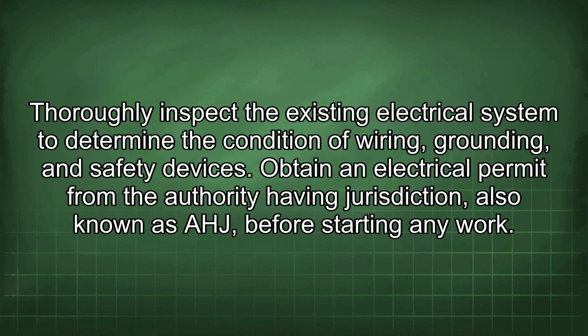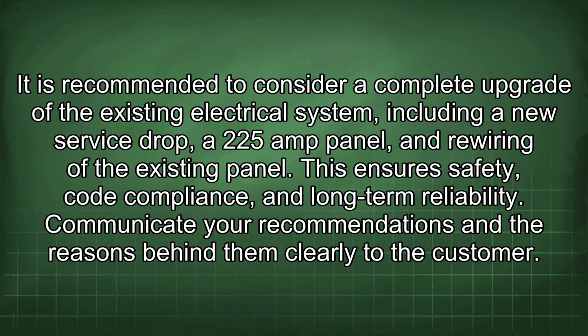Thoroughly inspect the existing electrical system to determine the condition of wiring, grounding, and safety devices. Obtain an electrical permit from the authority having jurisdiction, also known as AHJ, before starting any work. It is recommended to consider a complete upgrade of the existing electrical system, including a new service drop, a 225 amp panel, and rewiring of the existing panel. This ensures safety, code compliance, and long-term reliability.